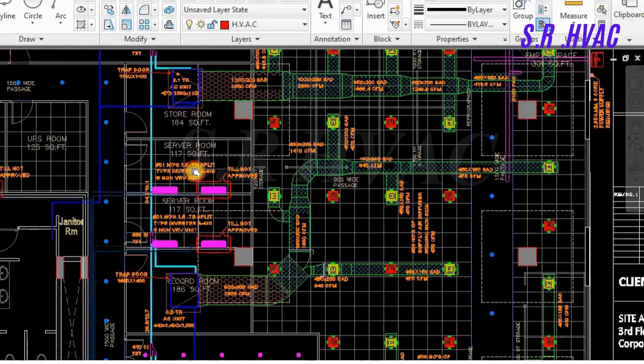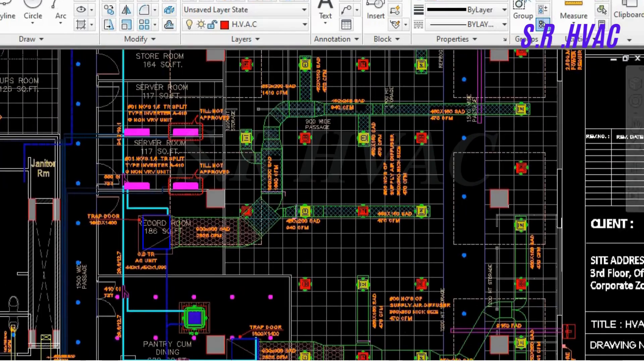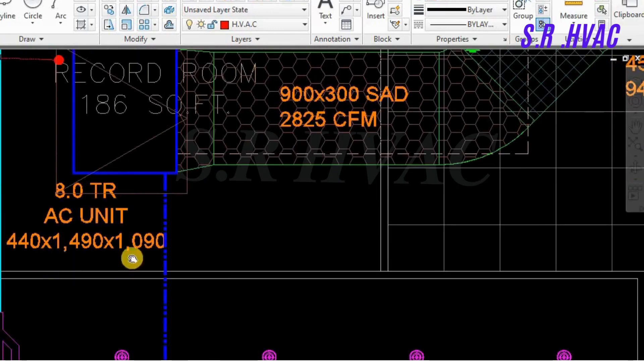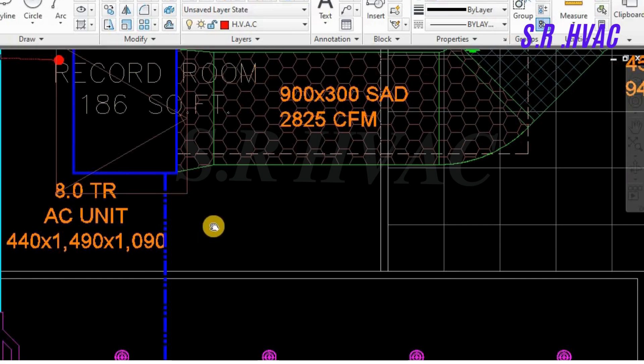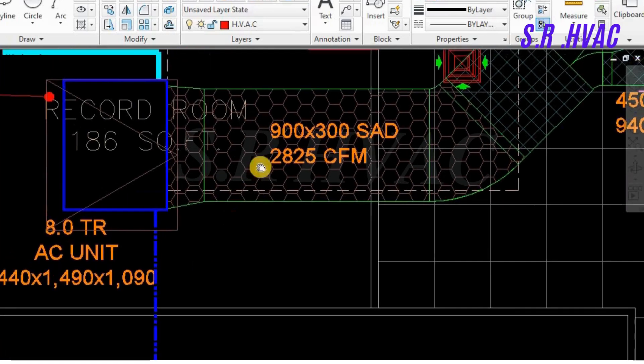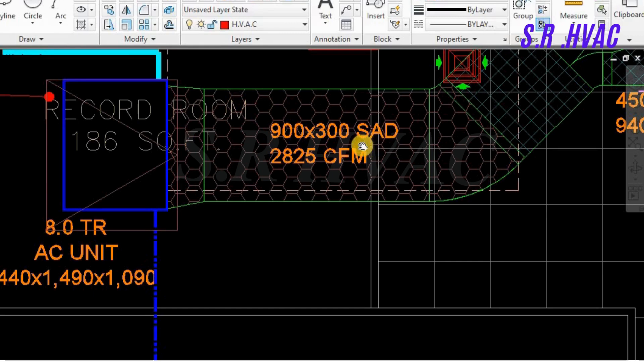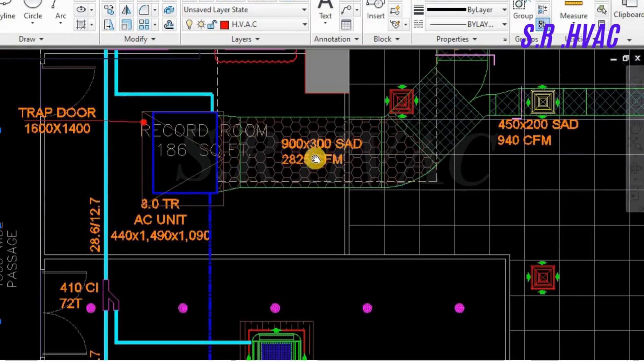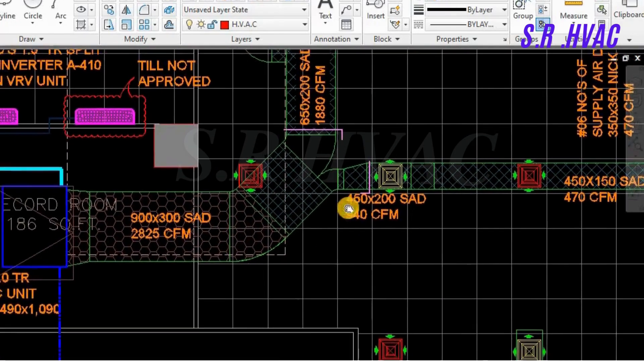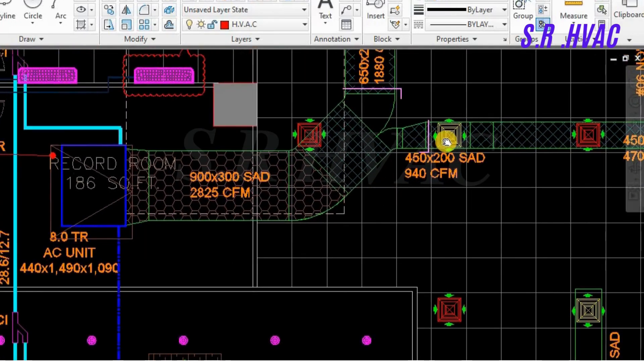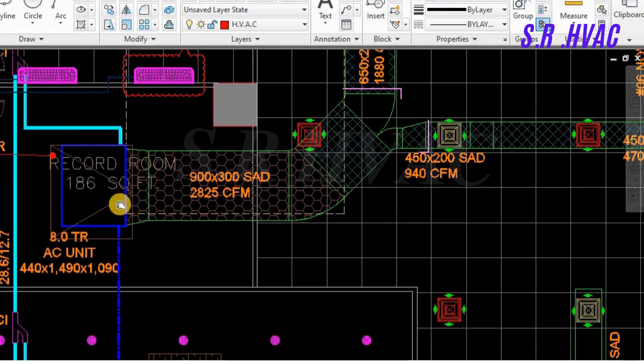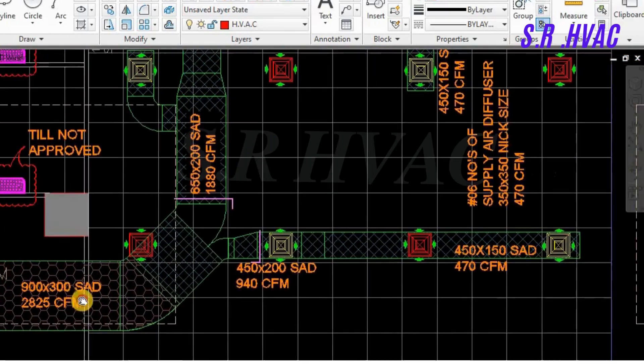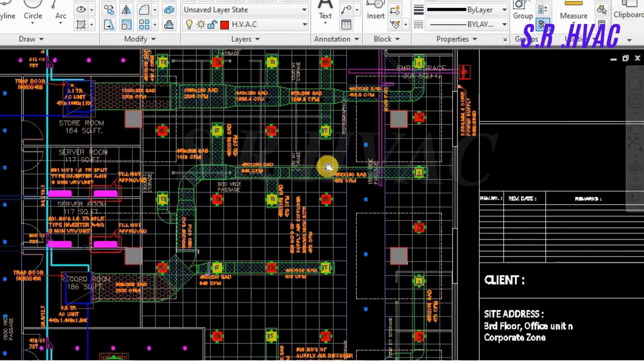Friends, we will see one ductable unit also. So we will take up this 8TR ductable unit, the Daikin. You can see 440, 1490 and 1090. The CFM will be 2825 CFM. And the duct size is taken 900 into 300 as SAD. So it is abbreviation for supply air duct. This is the short form. The abbreviation is supply air duct, and you should know what is RAD, return air duct. Friends, this is the supply air diffuser, then this is the return air diffuser. In the front of the ductable unit we will have a canvas so that no vibration is transferred, then it will be acoustic insulation. This is the ducting in the front, you will have acoustic insulation and rest it will be the thermal insulation.